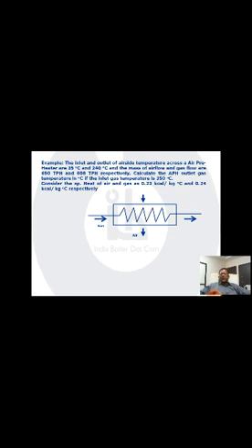Now just note down on paper the data which has been provided. What has been given? They have given you the air temperature in and out, the mass of air and mass of gas, the gas inlet temperature, and the specific heats, right? So the air is 650 tons per hour with 35 degree inlet and 240 degree outlet. The gas is 608 tons per hour with 350 inlet. The outlet is not known to us.